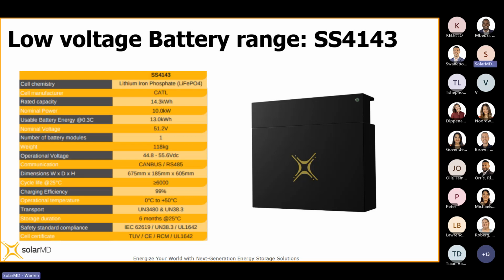The cell offers up to 6,000 cycles, and you'll note on the data sheet that it says this is at 25 degrees. So if it's sitting in a 35, 40, or 50 degree environment, the number of cycles the battery can perform is going to be a lot less.